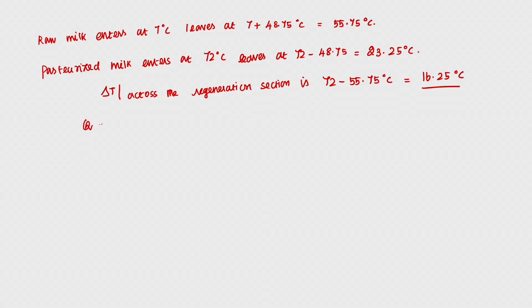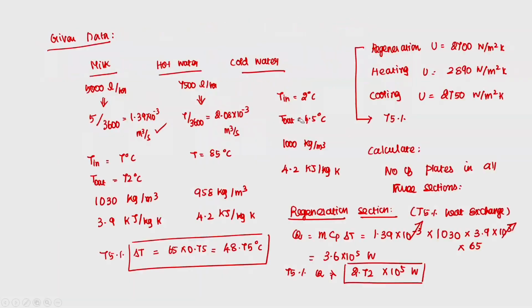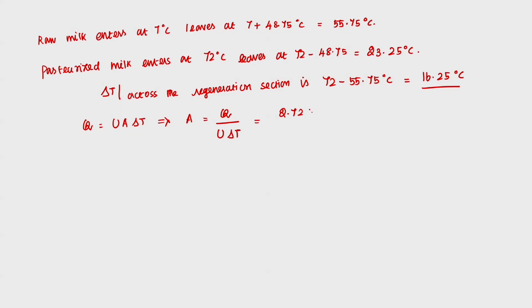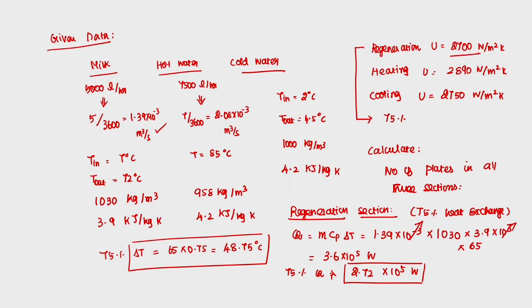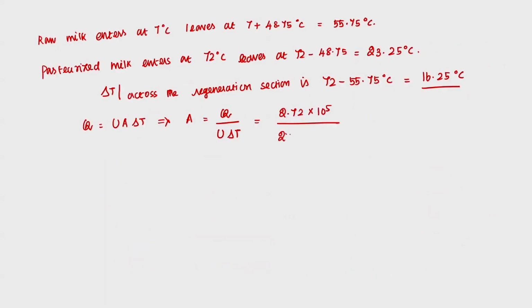We already know the formula, which is U A del T. So, what I need to calculate from here is A, which is Q upon U del T. We know the heat exchange, which is 75% of the total heat, calculated in the previous slide as 2.72 into 10 to the power of 5, upon U, which is given in the regeneration section as 2700, into del T which we just calculated as 16.25. This comes around 6.2 meter square.